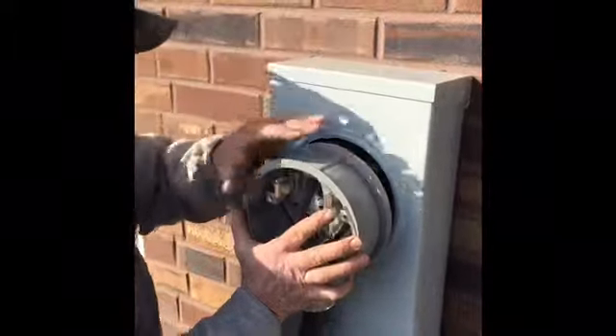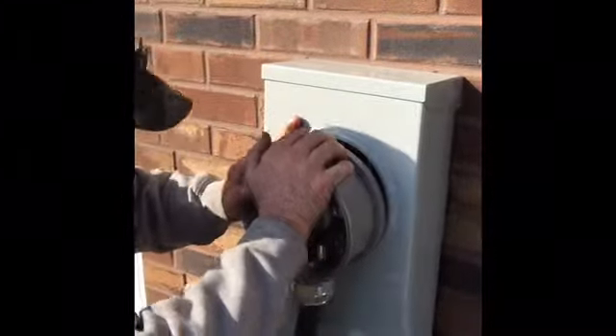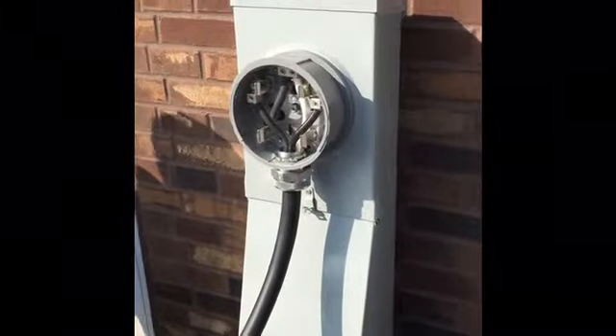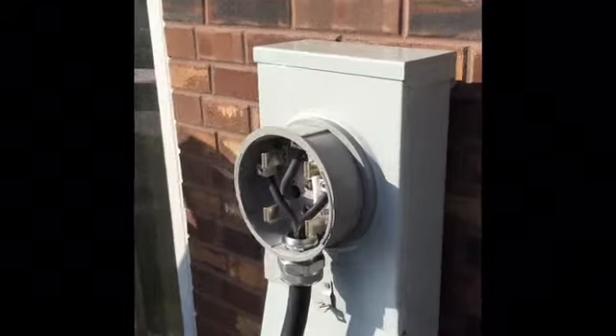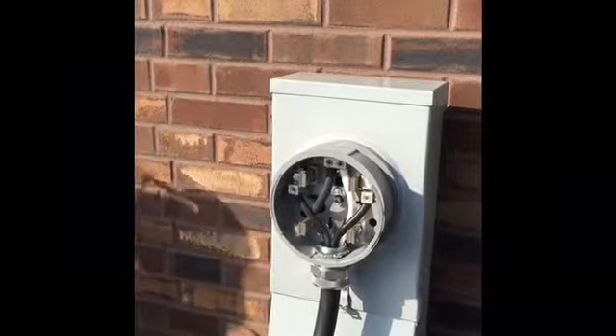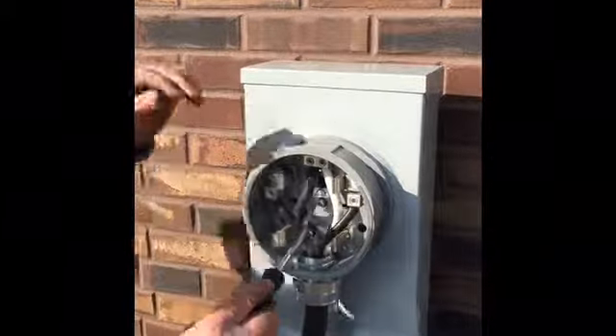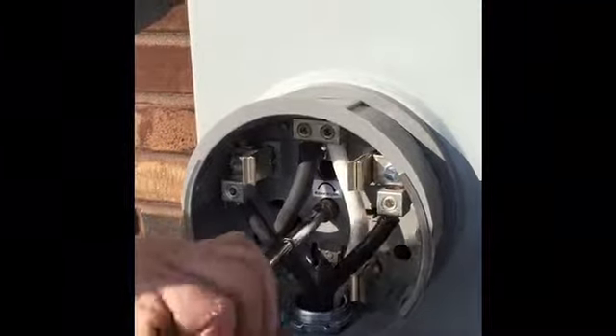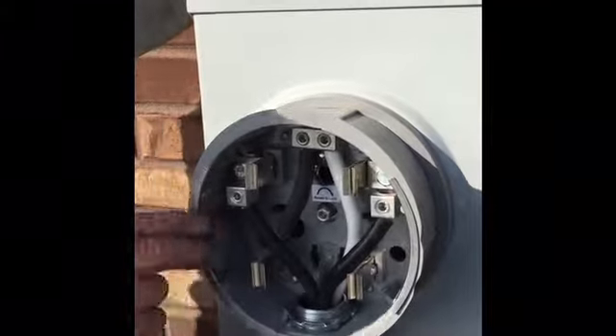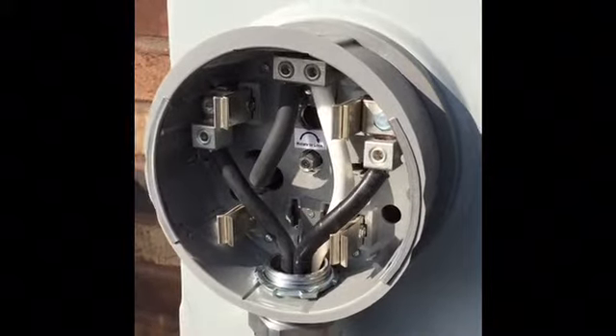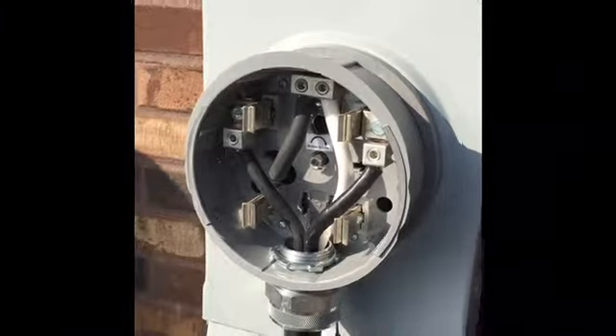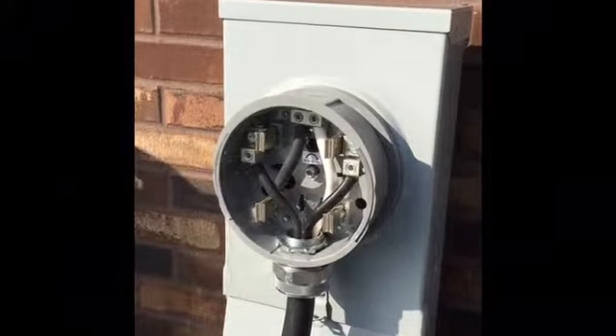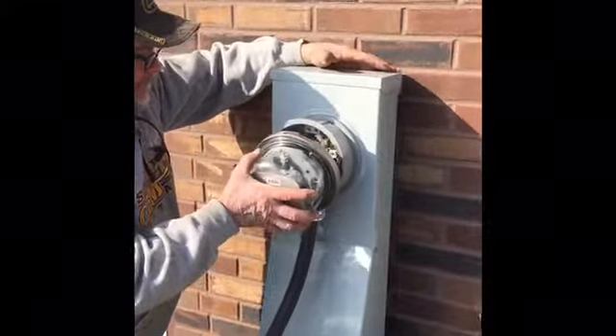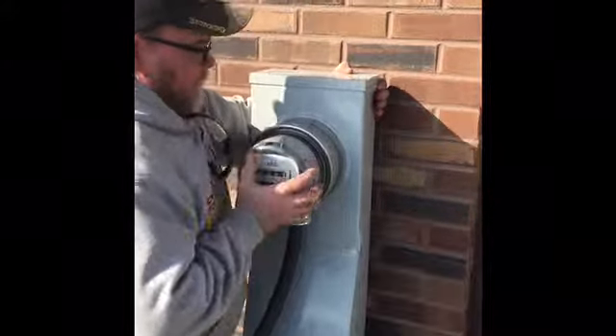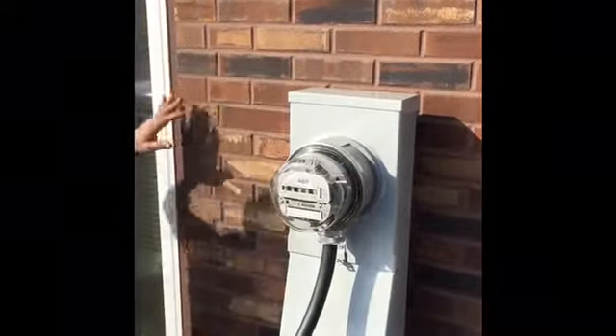Let's see, now we're installing the meter head into the jaws on the meter socket. Okay, so we got it pushed in there, and as you can see, it's flush with the outside of the meter socket. So then once you do that, the next step is to take a socket or a nut driver and turn a nut in the middle there. That's a cam action system with locking tabs. Once you turn that nut, I think it's just a quarter turn, the locking tabs from the cam pop out and grab onto the meter cover, so you can't pull that off of the meter socket cover there. So then the next step after that is we get our meter put in there. We're getting close to operation.